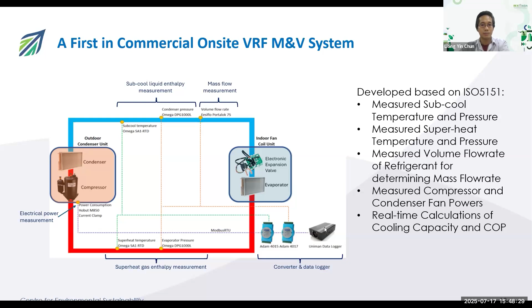And we are using an ultrasound flow meter to measure the flow rate of the refrigerants. So it's very similar to the chiller plant way of measuring the efficiency. The challenge in this case is that the ultrasound flow meter can only measure volume flow rate, but we need mass flow rate. That's why we have the program there. We built in a controller to collect all the data, and we calculate the density of the refrigerant in real time based on the pressure and the temperature. And we also key in all the thermodynamic tables inside our controller to do these real-time measurements.